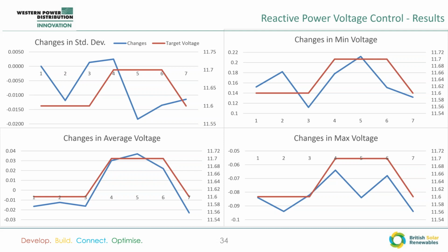But we're not seeing such a clear pattern in any of the other graphs. And the control data, again, is noisy as it's taken from the live network. But the battery, at this point, when I set it to 11.7, it was working at full capacity to try and influence. It was giving its full 310 kVAR, and we're still not seeing a very large effect.